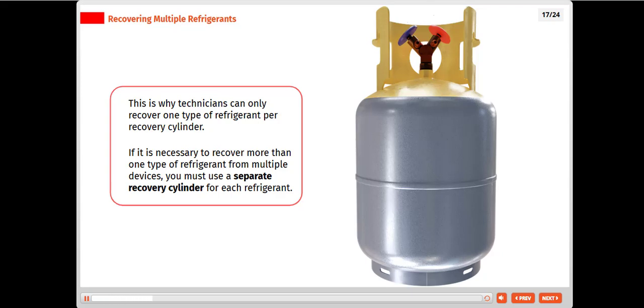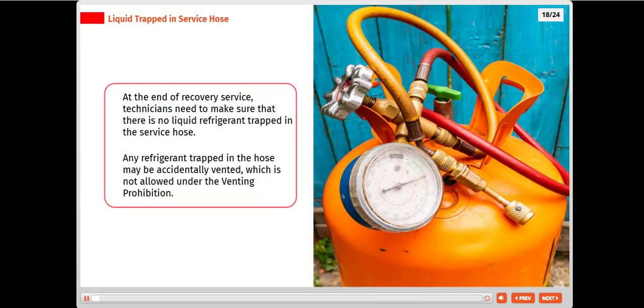This is why technicians can only recover one type of refrigerant per recovery cylinder. If it is necessary to recover more than one type of refrigerant from multiple devices, you must use a separate recovery cylinder for each refrigerant. At the end of recovery service, technicians need to make sure that there is no liquid refrigerant trapped in the service hose. Any refrigerant trapped in the hose may be accidentally vented, which is not allowed under the venting prohibition.